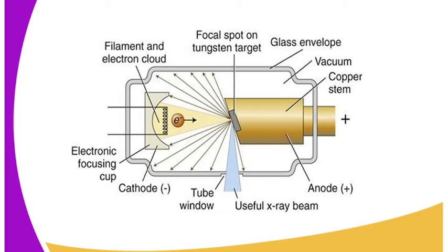The target must therefore be a metal of high melting point, such as tungsten or molybdenum. The anode is made of a good conductor of heat, like copper, to ensure efficient dissipation of heat. In recent models, the target rotates during operation to change the point of impact. Some X-ray machines usually rotate, thereby reducing the wear and tear on it.